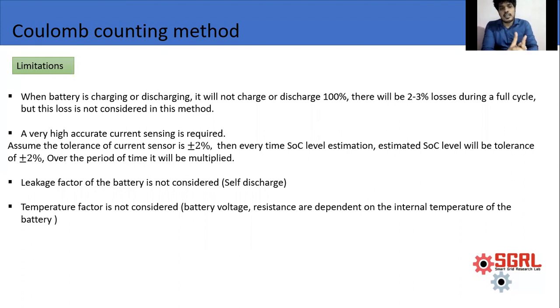A very high accuracy current sensor is required. Assume the tolerance of the current sensor is plus or minus 2%. Then every time SOC level is estimated, it will carry that tolerance of plus or minus 2%, and over time that error will be multiplied.